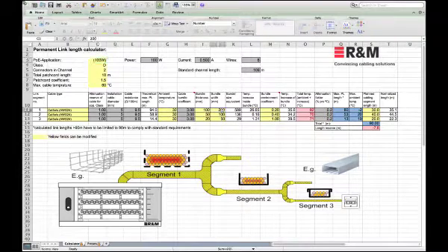Say, for example, my bundle wouldn't be 200 wide, but I would have 2 bundles of 100, each of the bundles would have a much lower temperature. So by just making 2 bundles instead of 1, we reduce the maximum temperature in the bundle by 20 degrees, going down to 71. But obviously that's not enough.